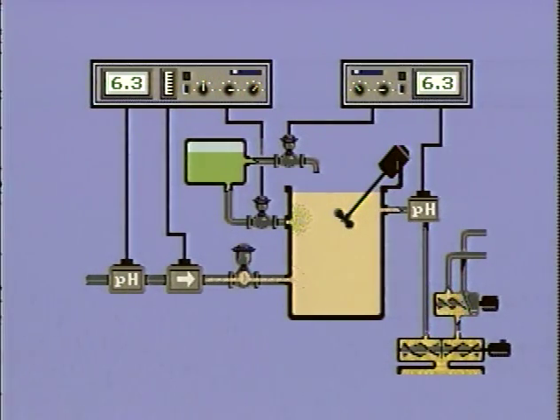The addition involved adding a second pH instrument downstream of the mix tank and an additional acid supply line. If the concentration of the acid additive decreased, the feed-forward controller could not detect the decreased concentration and adjust to add additional acid to compensate. However, a downstream pH instrument would detect a pH error. The error signal caused the adaptive controller to adjust its action based on the size of the error and position the valve in the second supply line to add enough acid to compensate. Acid entered the mix tank in greater volume until the error was corrected.